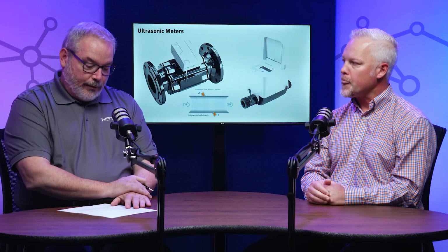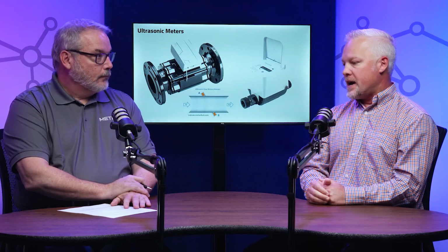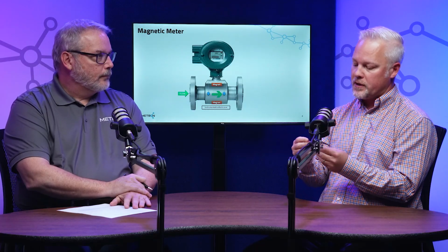Okay. And then the second type of static meter is a magnetic meter. Mag meters, yeah. So I would say probably less common, except for maybe in custody transfer. But essentially, the water has to have some dissolved salts or minerals for this to work. You're using an electromagnet across the tube, and as the water hits those dissolved salts, that's creating little bits of charge that you can detect as voltage, and so the faster it flows, the more you're building up that charge. Maybe a decent way to think of it would be like trying to measure static electricity for determining how fast a river is flowing. Okay.